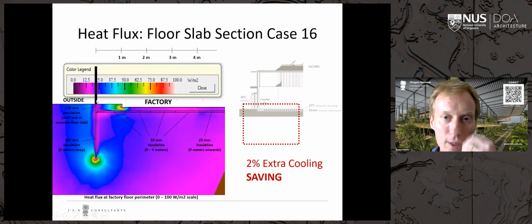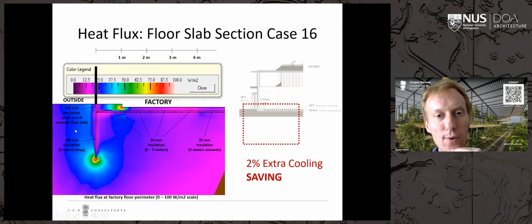We also looked at what if we dig down vertically 2 meters and put in an insulation layer, to force the heat to go deeper into the ground before it can reach the cool slab. But this wasn't practical and probably a bit expensive, because the groundwater level was quite high for this site, and the insulation would float up. So we didn't do that.